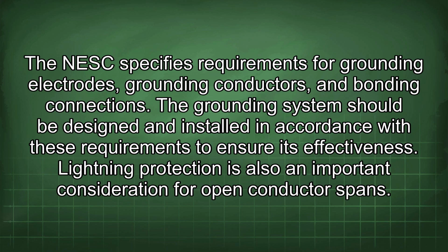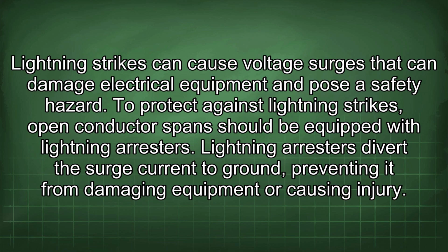Lightning protection is also an important consideration for open conductor spans. Lightning strikes can cause voltage surges that can damage electrical equipment and pose a safety hazard. To protect against lightning strikes, open conductor spans should be equipped with lightning arresters. Lightning arresters divert the surge current to ground, preventing it from damaging equipment or causing injury.